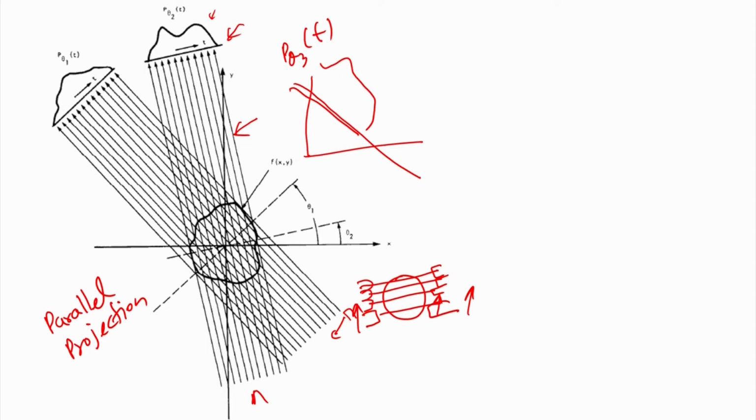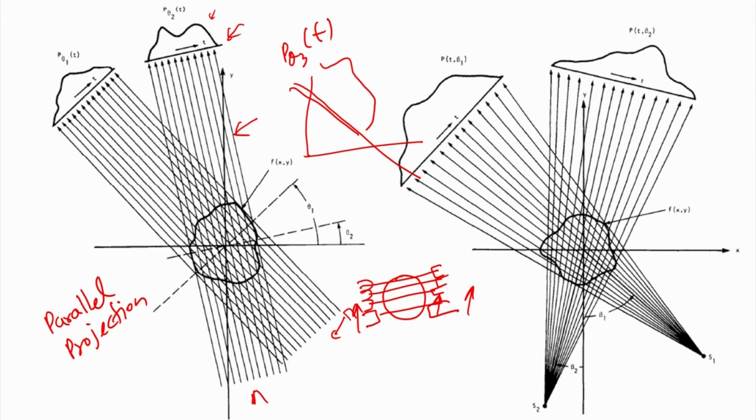So, that is why a different type of beam is being preferred, which is called fan beam. What we do is use one source, as I said here, and several detectors, as we discussed in the previous photograph also. We make a fan beam, we make a curvature of this collimator in such a way that you generate a fan of a particular angle, and we keep the distance in such a way that this fan angle covers the entire range of interest. And for each ray there is a detector available which is acquiring that data.